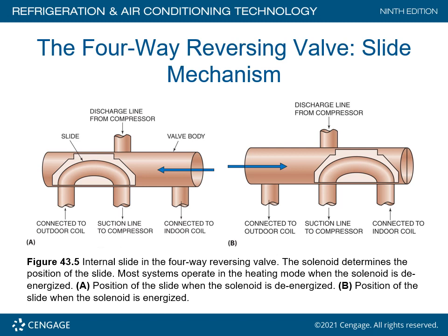Now this four-way valve is either going to be energized or de-energized depending on the manufacturer. There is no one-size-fits-all operating scenario amongst all the manufacturers in the United States, and for that matter, other countries that manufacture heat pumps. So in this case here, depending on if the solenoid is energized or de-energized in position A, we are going to show what happens to the refrigerant.